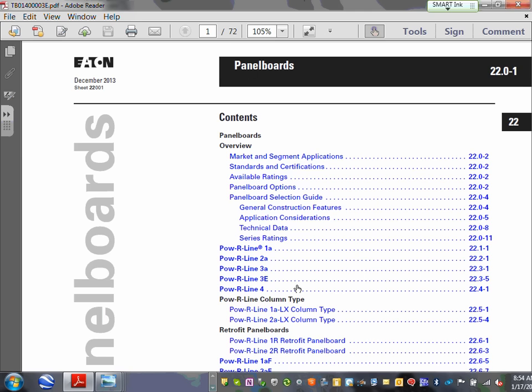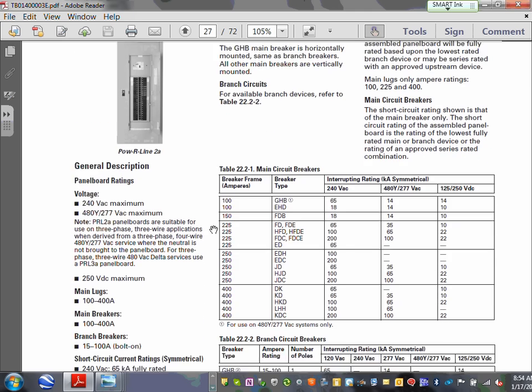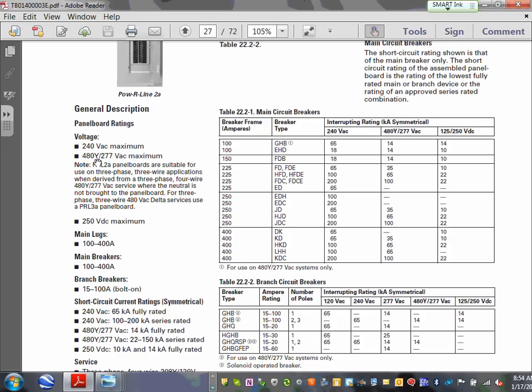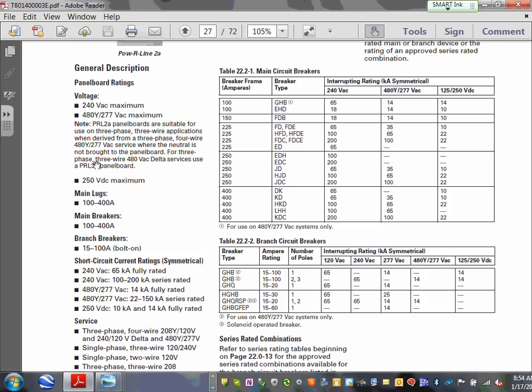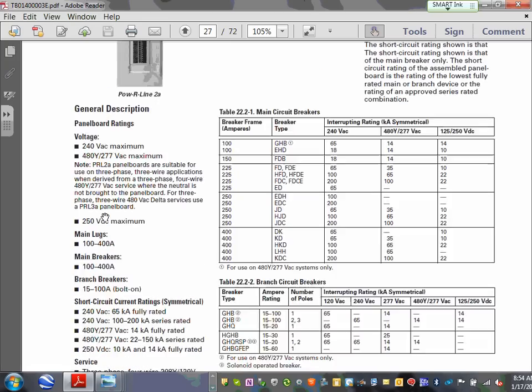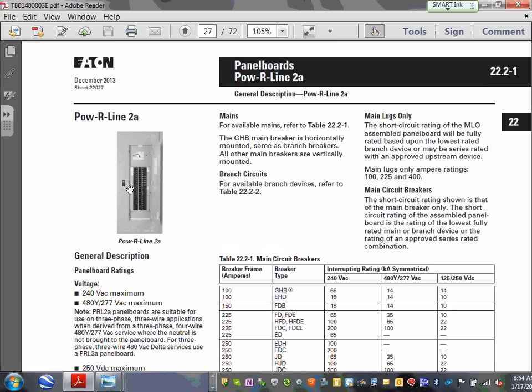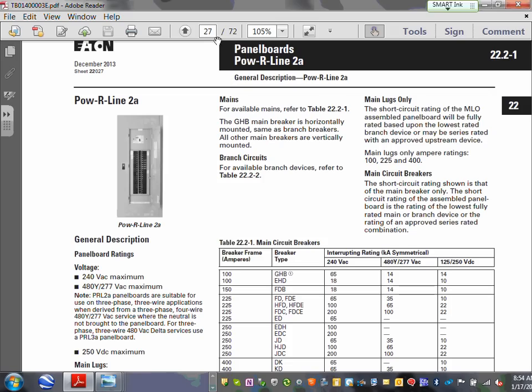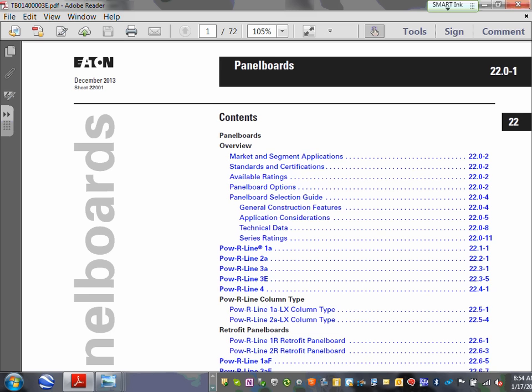If you go to 2A, it goes all the way to 480. Now you can power 480. Our lighting panel is going to be 480. And circuit breakers and lugs, both of them can go up to 400 amp. That panel, Adam, is going to be your panel for your receptacle, for your lighting panel. When they say cut sheet for lighting, you're going to be bringing this one for your friend Chad. Okay? These are all directly from Cutler-Hammer.